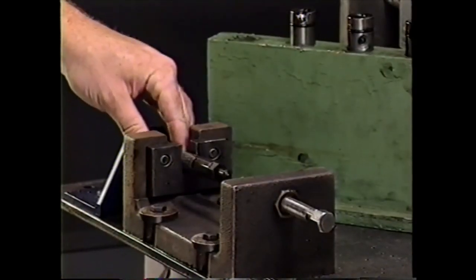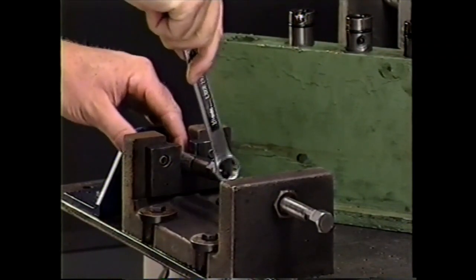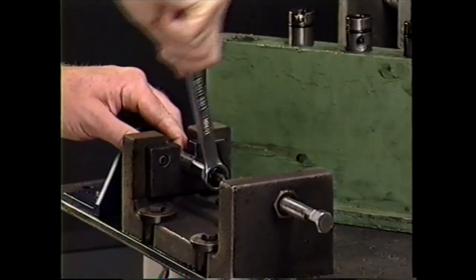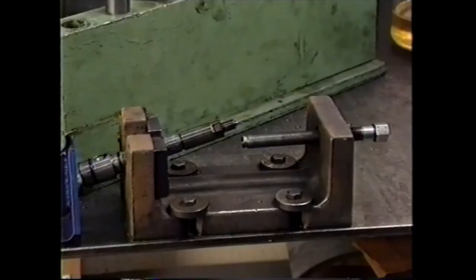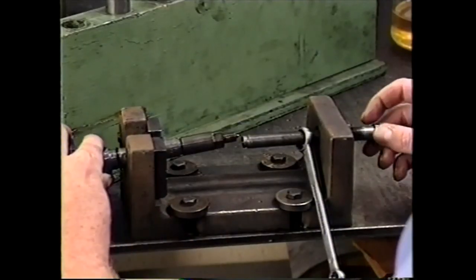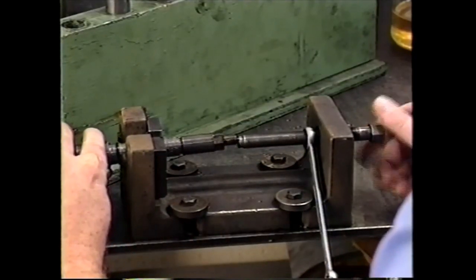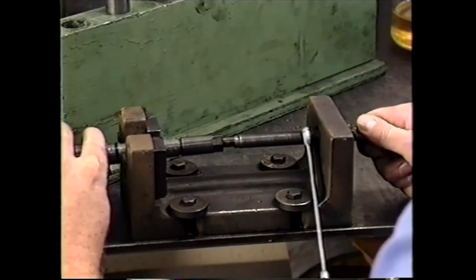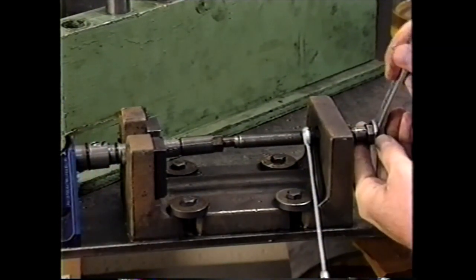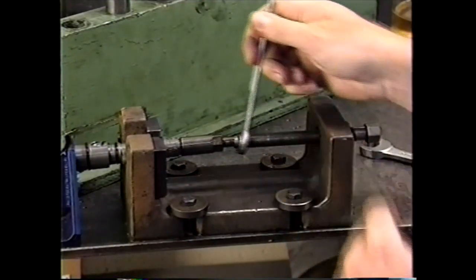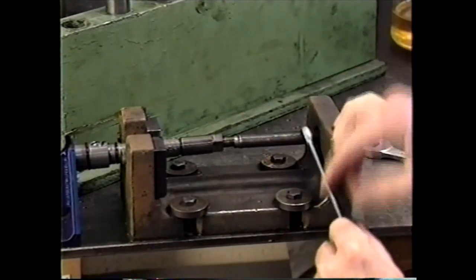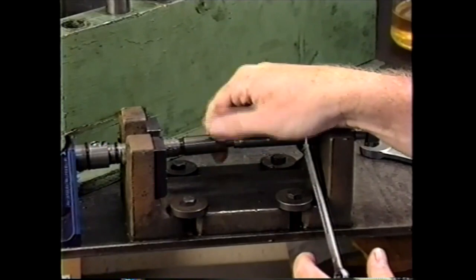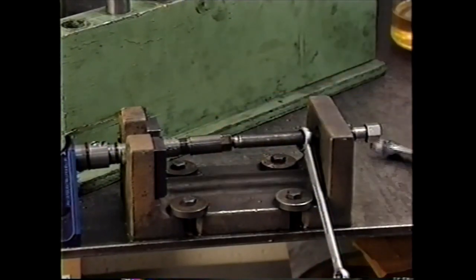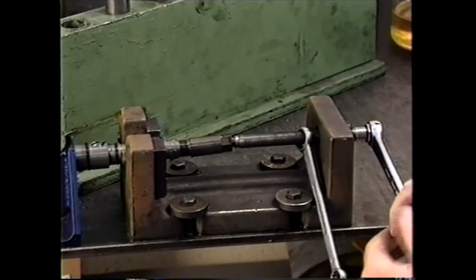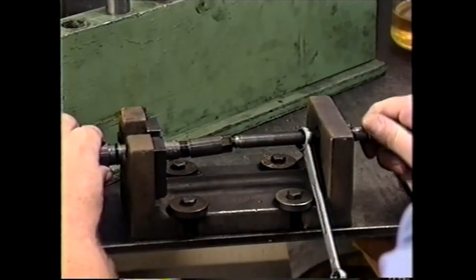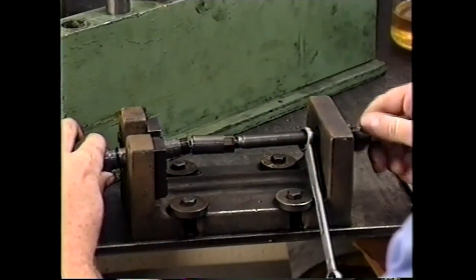Place the nozzle holder in the proper fixture and loosen the nozzle nut 1/8 of a turn. Next, to prevent shearing the dowels in the nozzle holder, relieve the spring pressure on the nozzle tip by clamping the tip to the nozzle body. Then loosen the nozzle nut until it can be removed by hand. This process prevents spring pressure from damaging the nozzle nut threads and contaminating the nozzle holder with metal chips.